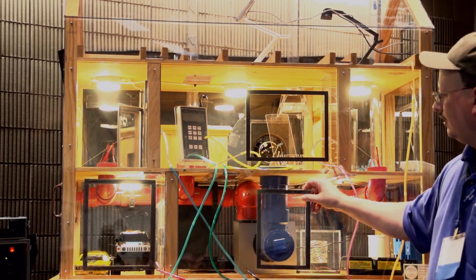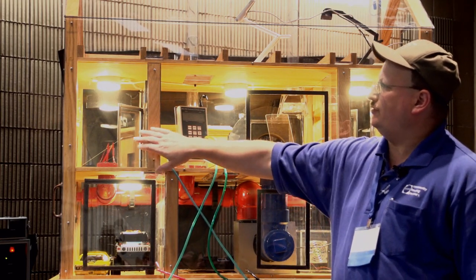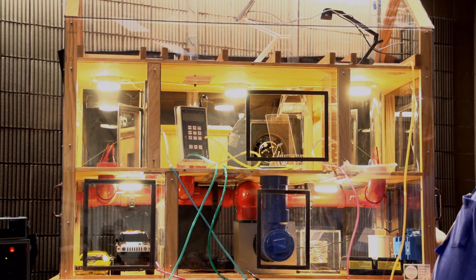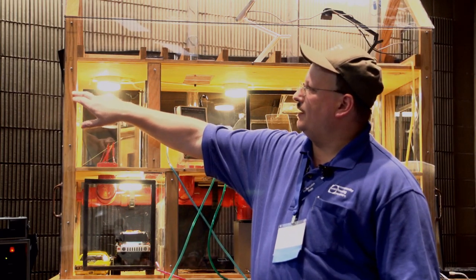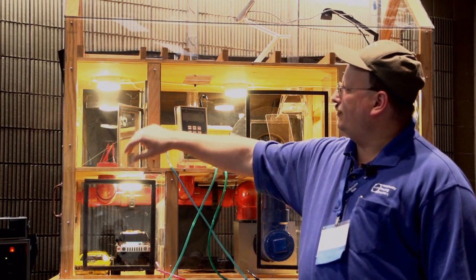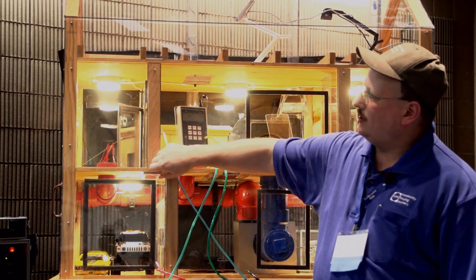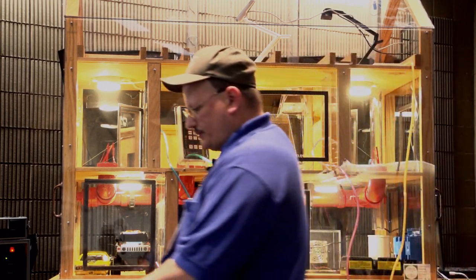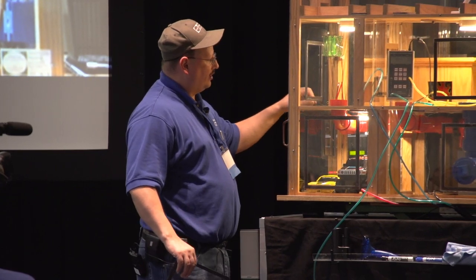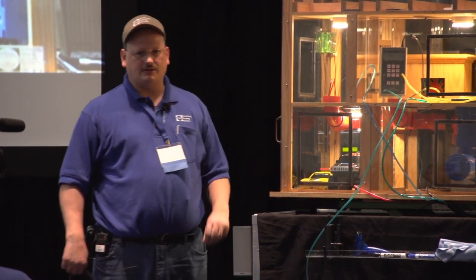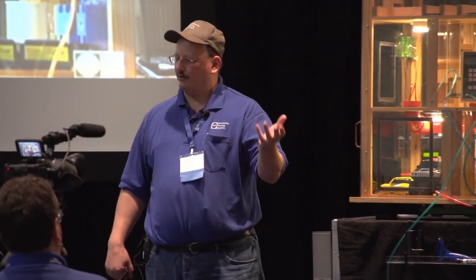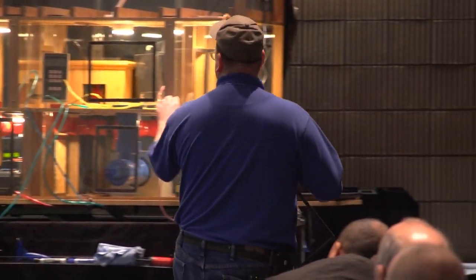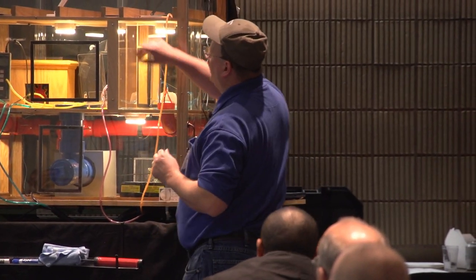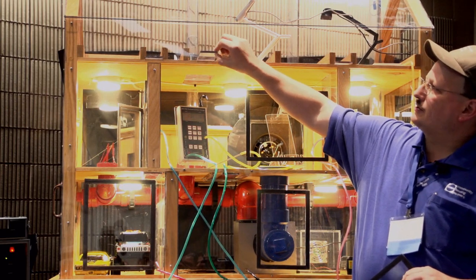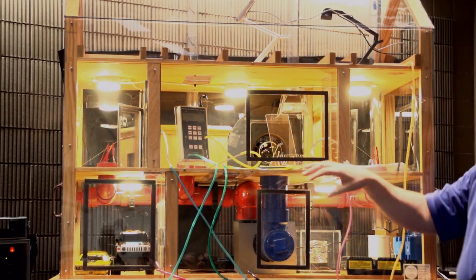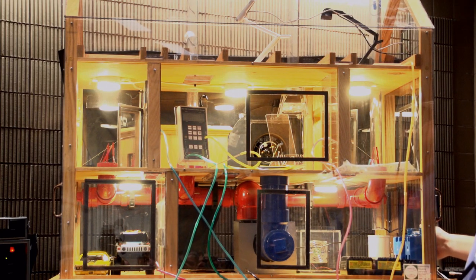Close those back up. Up here, this is more like a bathroom. We have a fan. It's probably not showing up in the video, but there's a fan over here. There's bypasses we can open at the top and the bottom here. There's also interior doors that we can open and close. When you do the blower door test, are those interior doors open or closed? Yeah, the interior doors are open. Okay. And the same thing over here, I've got more bypasses, another door. At the top, we got a bypass. This right here is like an attic access, and we'll open those. And there's a fireplace and a water heater that we can use for testing too.